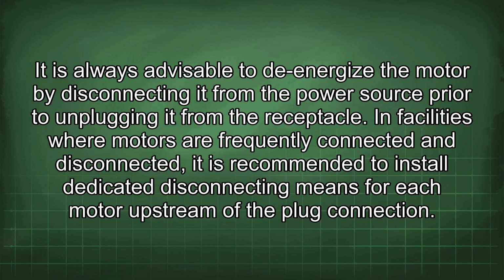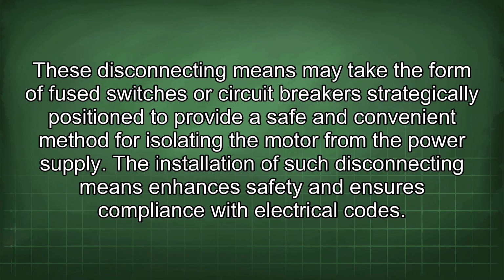It is always advisable to de-energize the motor by disconnecting it from the power source prior to unplugging it from the receptacle. In facilities where motors are frequently connected and disconnected, it is recommended to install dedicated disconnecting means for each motor upstream of the plug connection. These disconnecting means may take the form of fused switches or circuit breakers strategically positioned to provide a safe and convenient method for isolating the motor from the power supply. The installation of such disconnecting means enhances safety and ensures compliance with electrical codes.